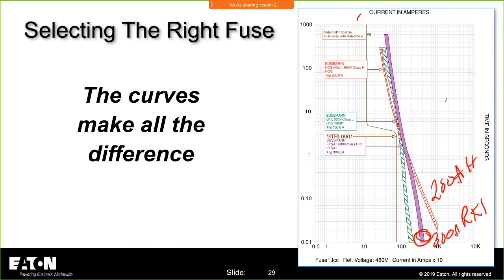And you'll notice the difference between the RK1 and the Class J. With the RK1, it takes more current to get into the current limiting region, but my Class J will still let this motor start, and provide better short circuit protection because I'll go faster. I'll be further into the current limiting region because I cross 0.01 seconds with this Class J at a lower current value than that RK1. So the Class J fuse probably would give you better short circuit protection for this motor, and it would still let the motor start, and would be a better performing fuse for you depending on what your goals are, whether it be price or damage, etc.